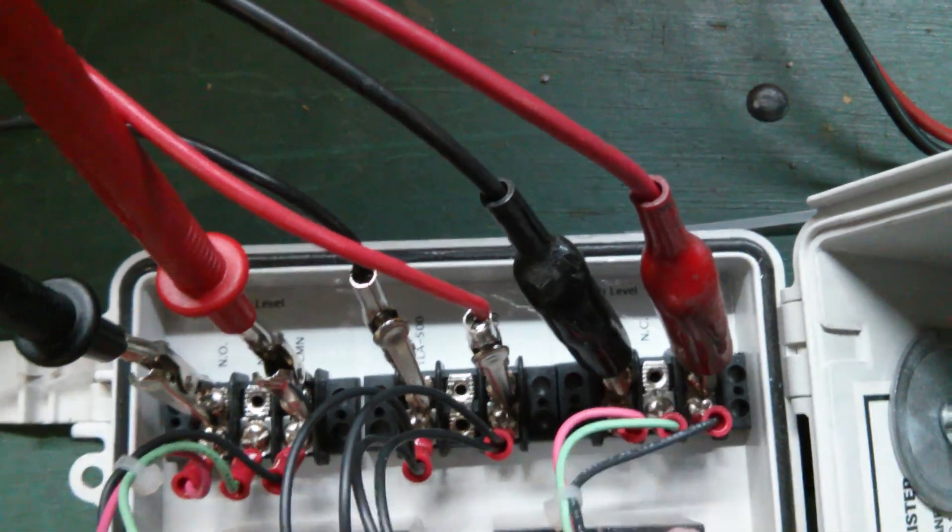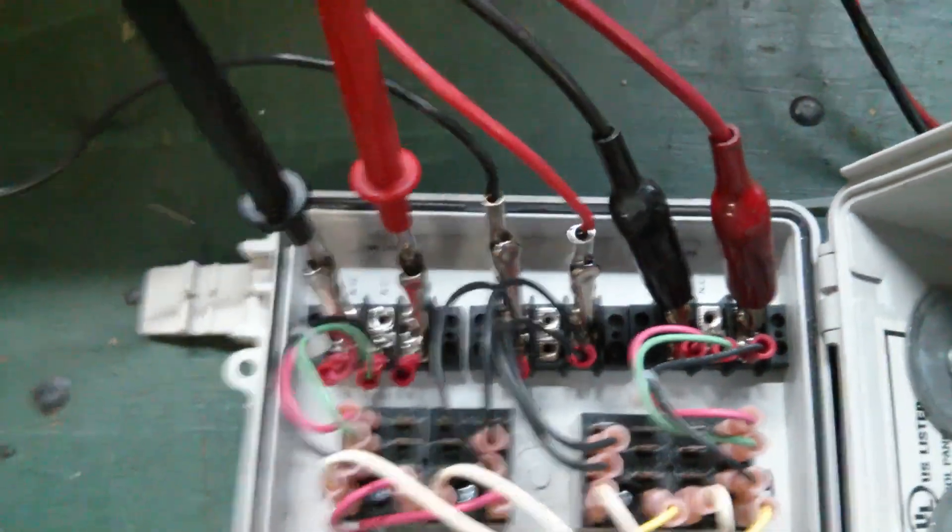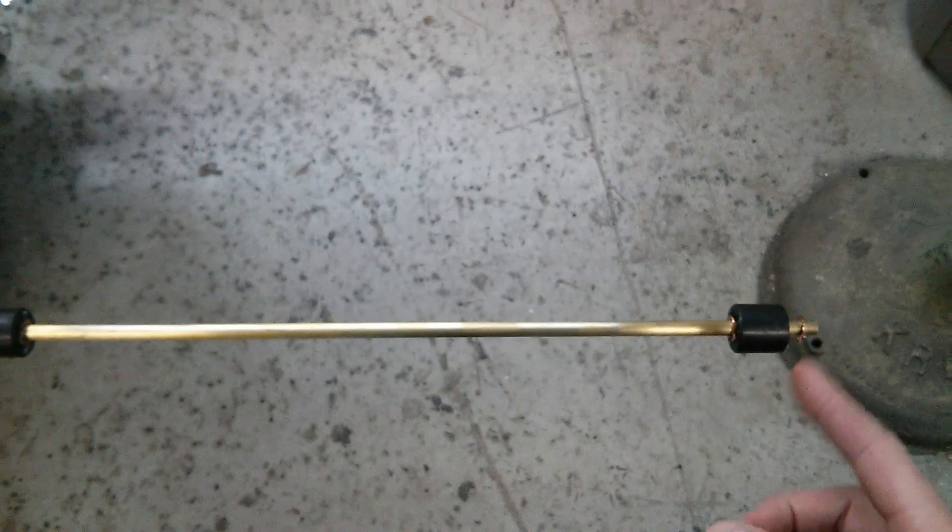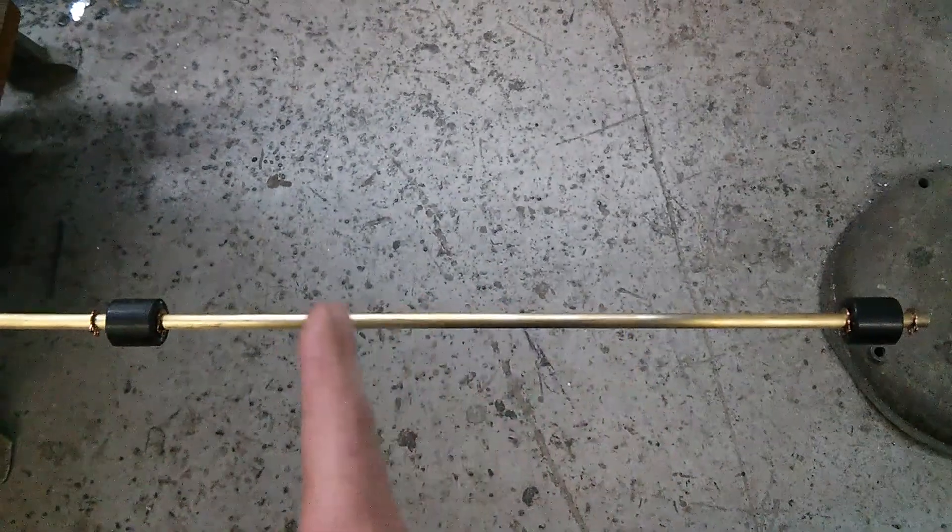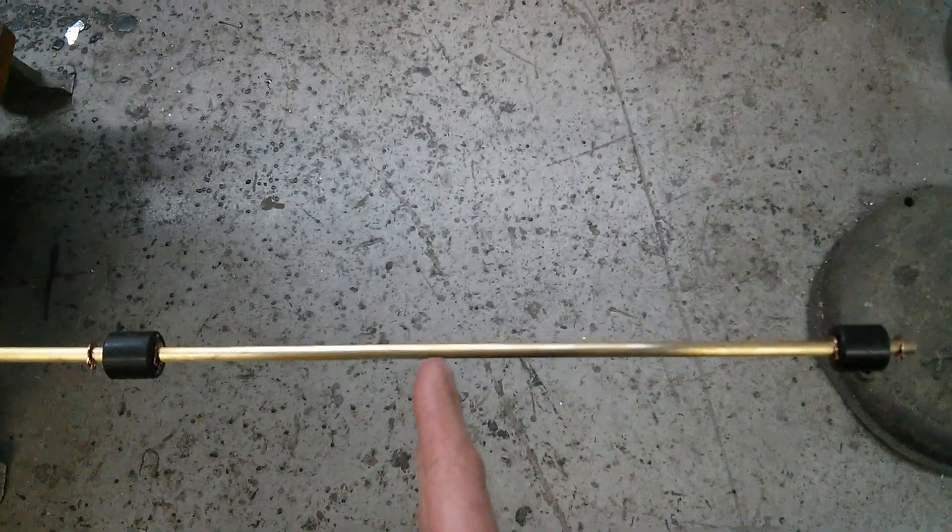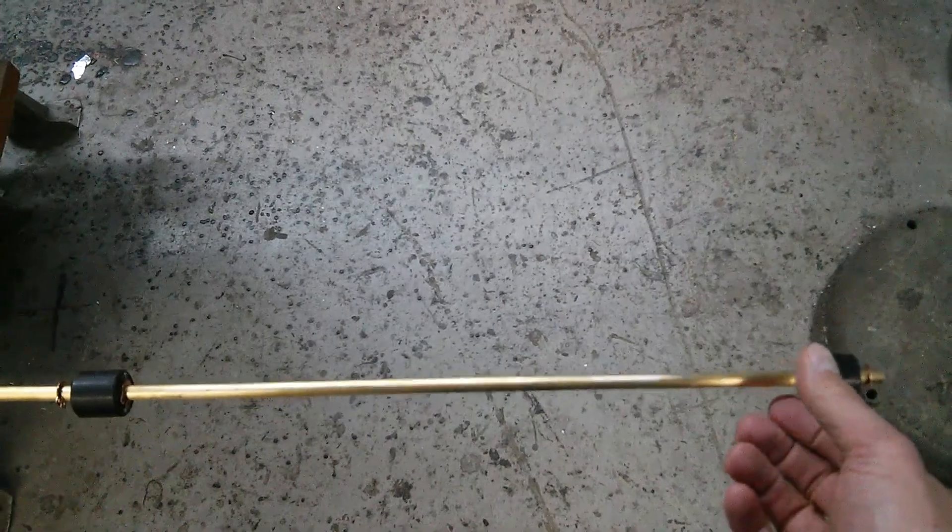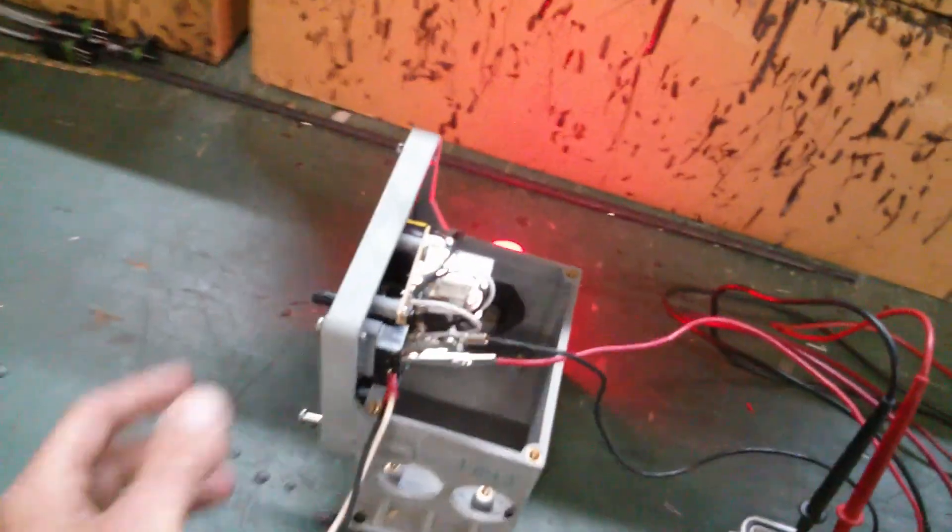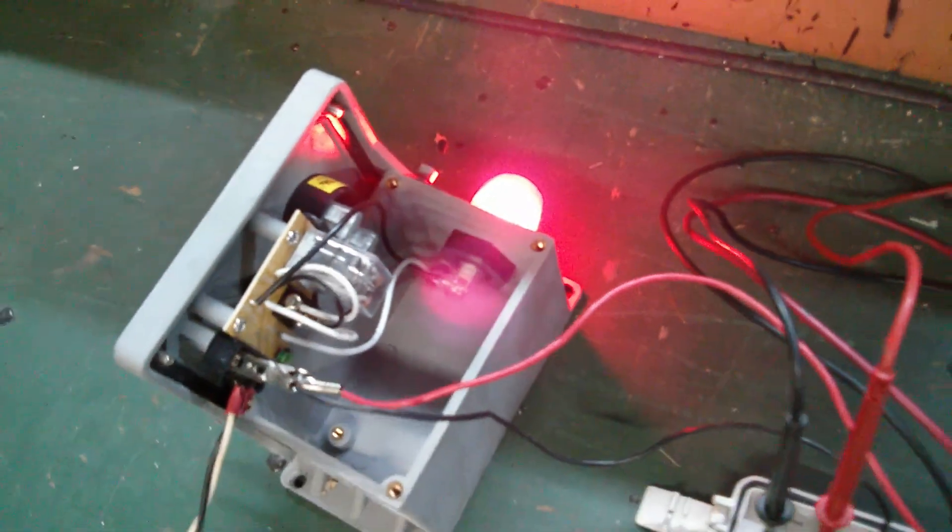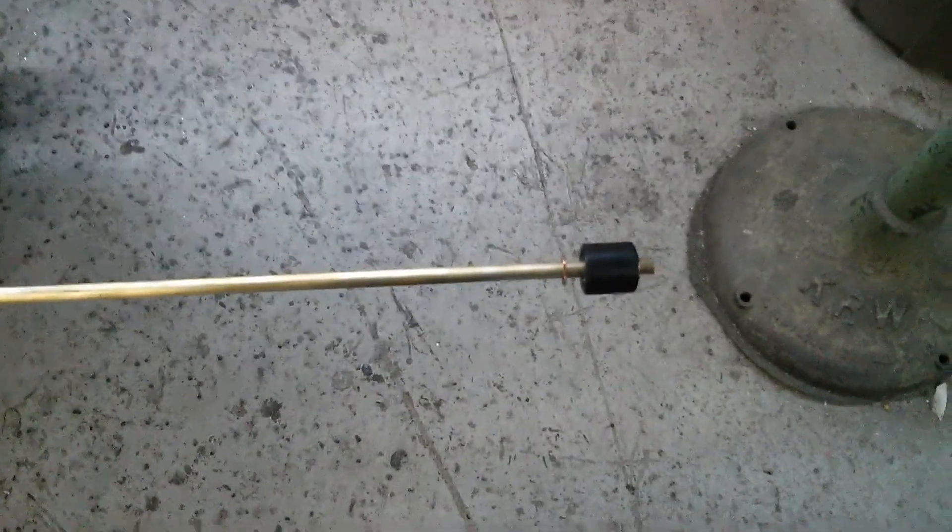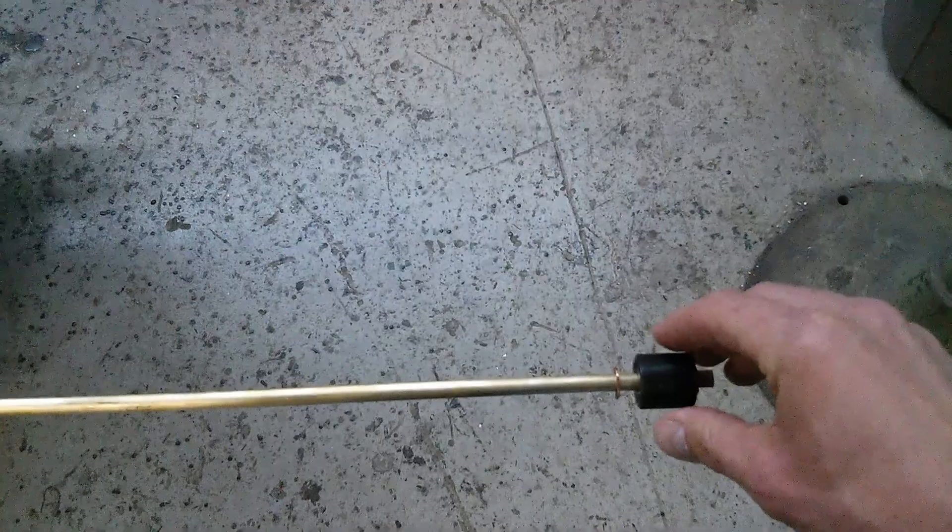So we're plugged in, we're powered up. I have the floats, this one is up, so we're assuming the level is somewhere here in the middle. If the level were to drop and this float were to go down, the alarm sounds. The light stays on but you can silence the alarm, telling you you have a low level.